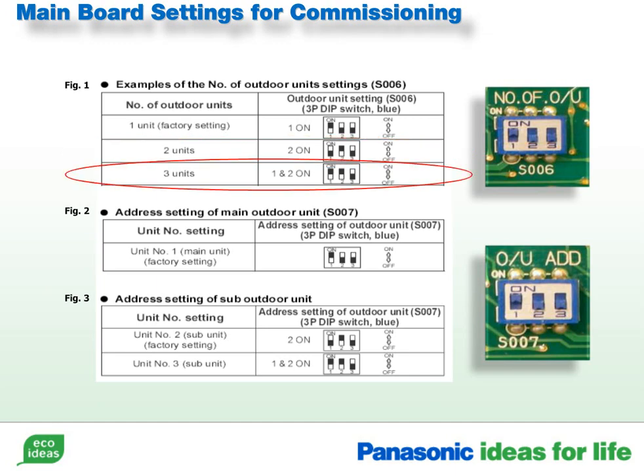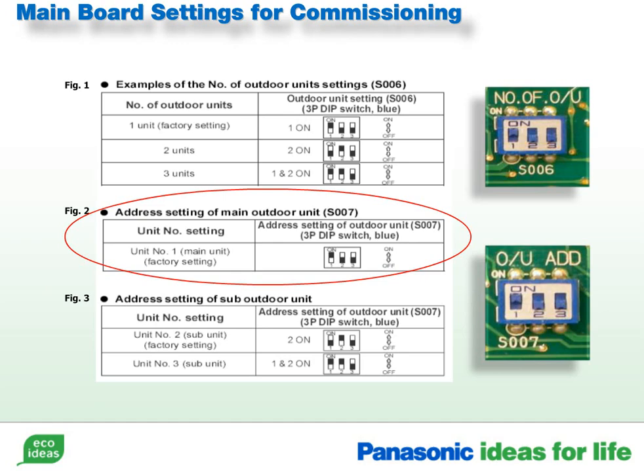When combining 3 outdoor units, the main board, on the main unit, will need to be configured to 3 outdoor units. This is accomplished by setting the dip switches 1 and 2 in the on position, and dip switch number 3 should be in the off position. Now we have to configure the outdoor unit address. The condensers come from the factory set as the main unit.